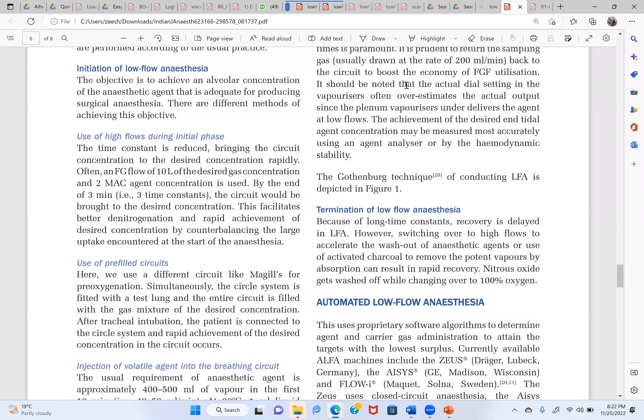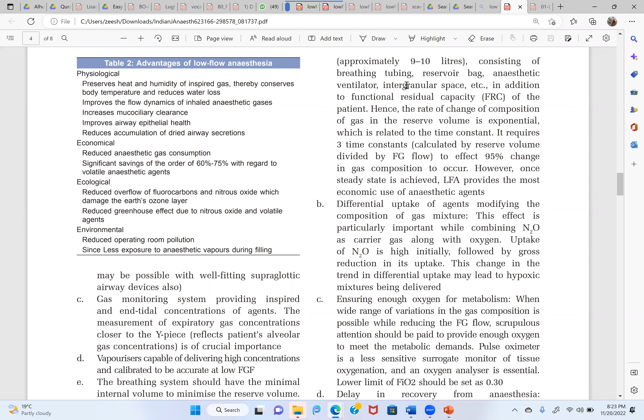Okay, so these are the advantages. We will just have a look. Preserve heat and humidity of respired gases, body temperature, and reduce water loss. Improves the flow dynamics of inhaled anesthetic gases. Increases mucociliary clearance. Improves airway epithelial health. Reduces accumulation of dried airway secretions. Economical, reduces anesthetic gas consumption. Significant saving of the order of 60 to 75% with regard to volatile anesthetic agents. And of course, the fluorocarbons and the ozone layer, the greenhouse effect. Reduced greenhouse effect due to nitrous oxide and volatile agents. Environmental, reduces operation room pollution.